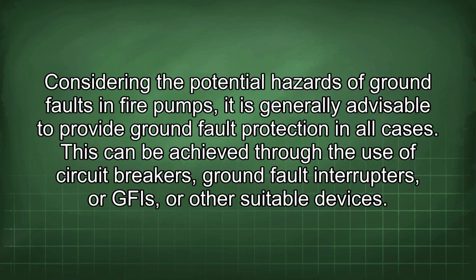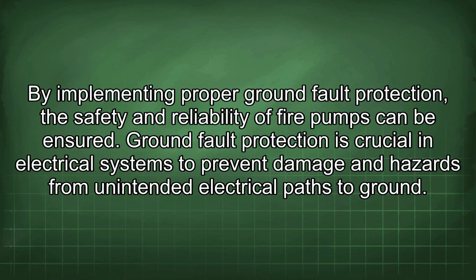Considering the potential hazards of ground faults in fire pumps, it is generally advisable to provide ground fault protection in all cases. This can be achieved through the use of circuit breakers, ground fault interrupters, or GFIs, or other suitable devices. By implementing proper ground fault protection, the safety and reliability of fire pumps can be ensured.